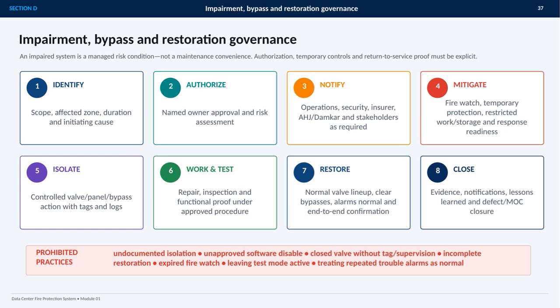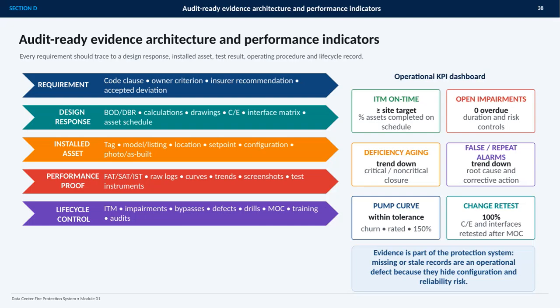This slide presents an audit-ready evidence architecture for the data center fire protection system. The central idea is simple. Every requirement must trace through the entire lifecycle. That means connecting the code clause, owner criterion, insurer recommendation, or accepted deviation to a design response, the installed asset, documented performance proof, and ongoing lifecycle control. In practice, that evidence can include calculations and drawings, asset tags and configurations, FAT, SAT, or IST results, raw logs and trends, inspection and testing records, impairments, bypasses, defects, drills, management of change, training, and audits.